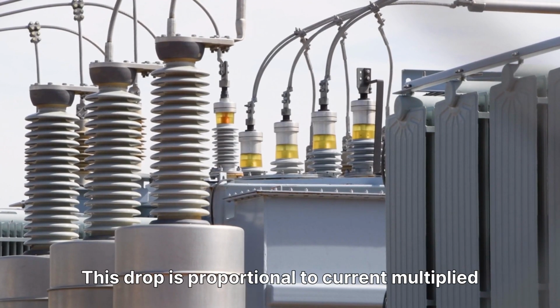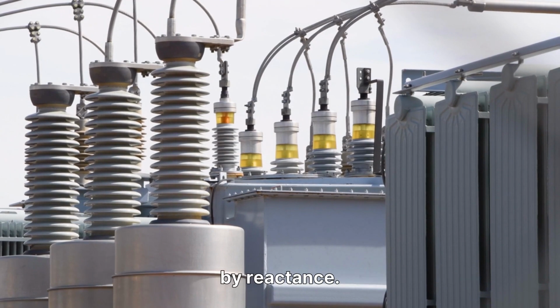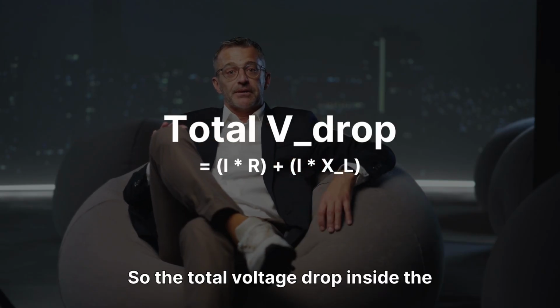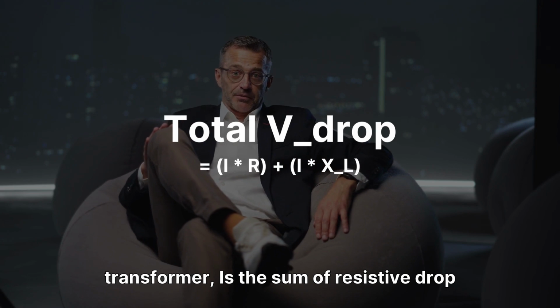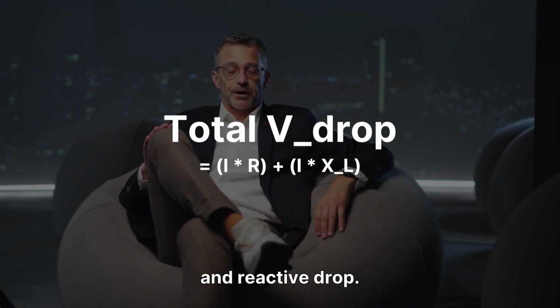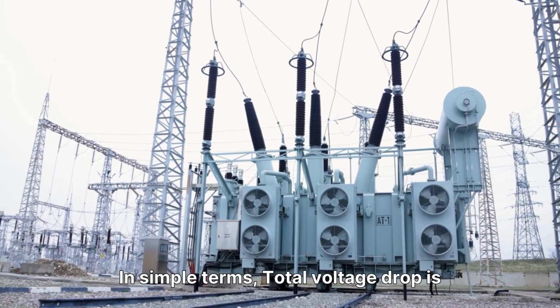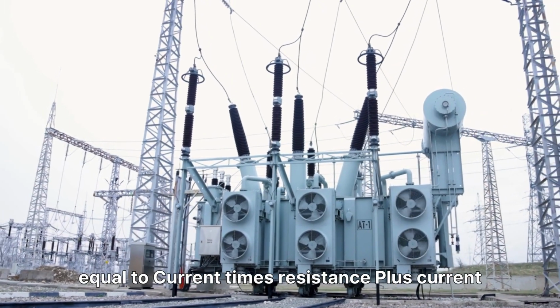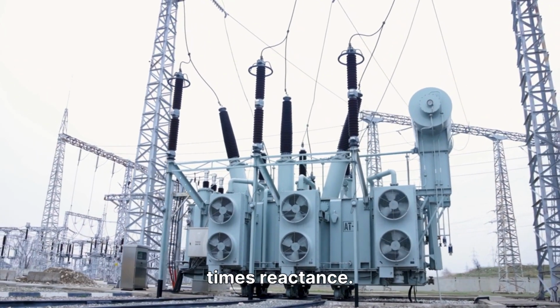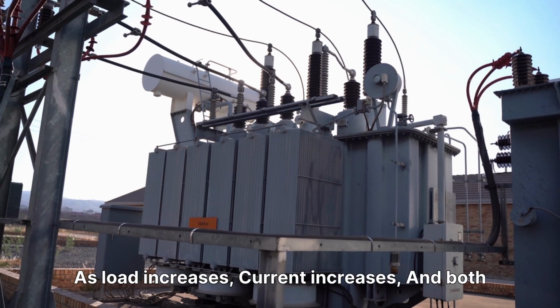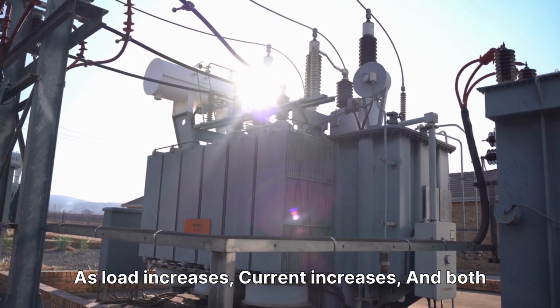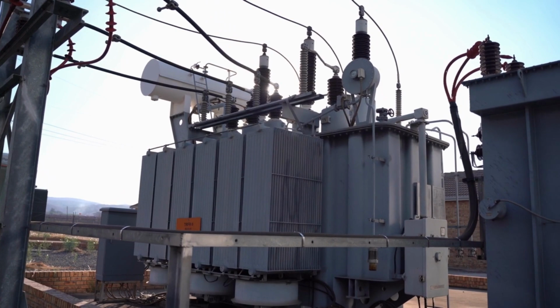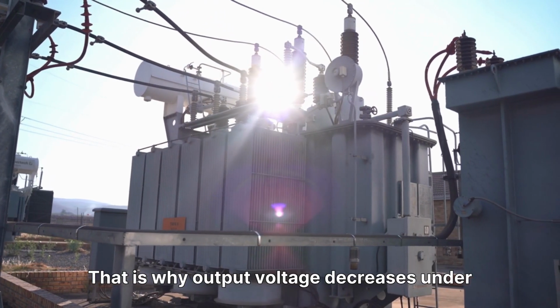This drop is proportional to current multiplied by reactance. So the total voltage drop inside the transformer is the sum of resistive drop and reactive drop. In simple terms, total voltage drop is equal to current times resistance plus current times reactance. As load increases, current increases, and both these voltage drops increase. That is why output voltage decreases under load.